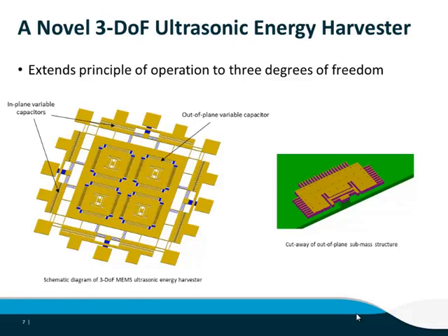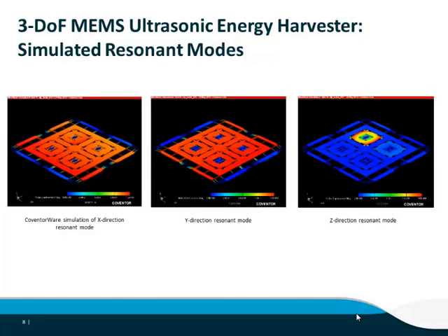So variable capacitors are formed due to the overlap between the comb fingers on each submass and the fingers on the surrounding structure. So effectively, each submass represents one electrode of a variable capacitor, and the surrounding structure represents a common electrode for each of these 4 capacitors. And again, each of the resonant frequencies of the device are tuned to around 40 kHz due to us using ultrasonic transmitters of this frequency. So these simulations show the resonant modes of the system. So in the in-plane directions, the whole central mass structure moves in unison, but the out-of-plane components involve just the relative displacements between each submass and the surrounding structure.